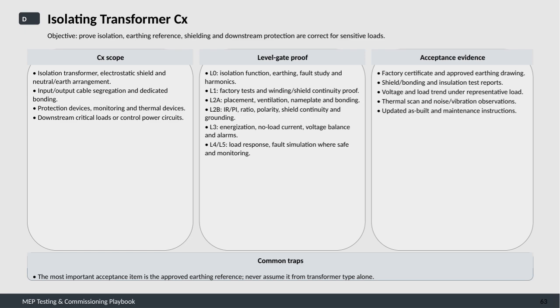Acceptance evidence includes factory certificates, approved earthing drawings, test reports on shielding, bonding, and insulation, as well as voltage and load trends under realistic conditions. Thermal scans help detect hot spots, and noise or vibration observations reveal mechanical issues. Updated as-built documents and maintenance instructions complete the package for handover. A common trap to watch out for is assuming the earthing reference based solely on the transformer type. The approved earthing reference is the most critical acceptance item and must be verified to avoid potential problems down the line.